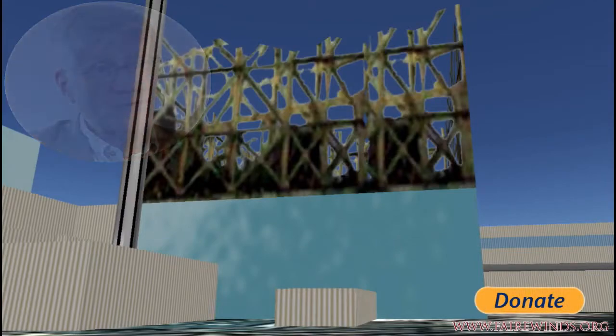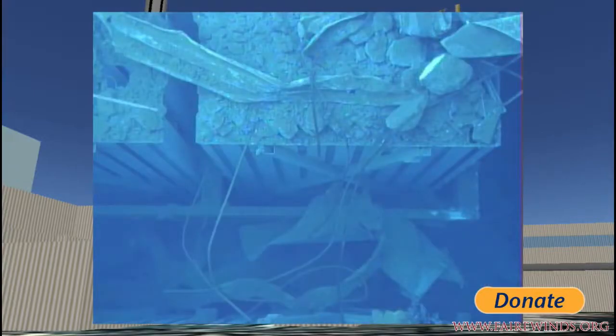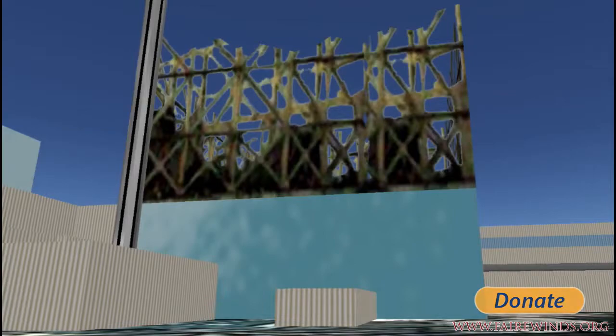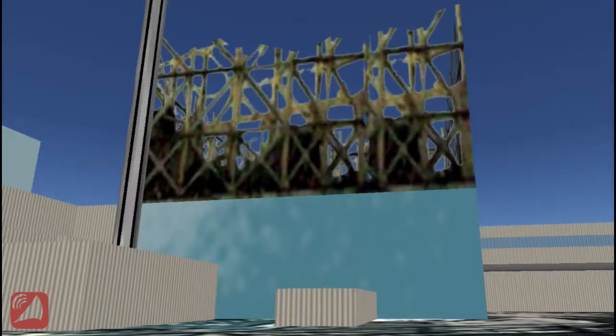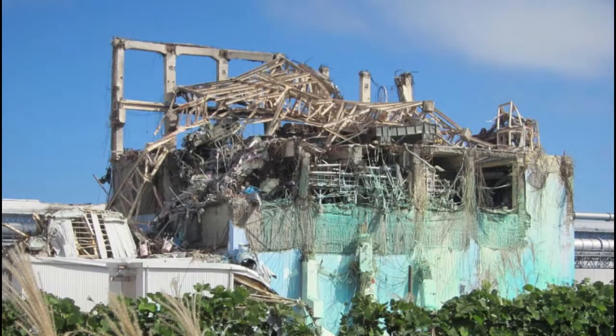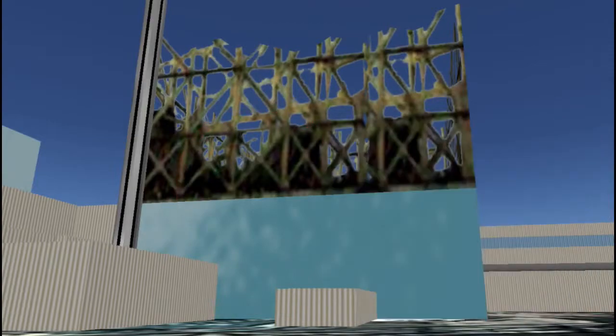Unit 3 has fuel in the fuel pool that eventually must be emptied, but radiation exposures are so high that personnel access is very limited. My biggest fear is that another earthquake — it doesn't have to be a Richter 9, even an 8.5 aftershock — could topple or shatter this building because it's been so badly damaged. It's being covered and will likely be completely wrapped in a shrink wrap cover by winter, but right now it's the only building exposed to the atmosphere.